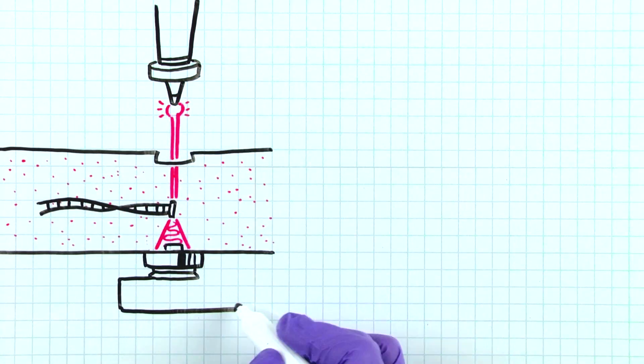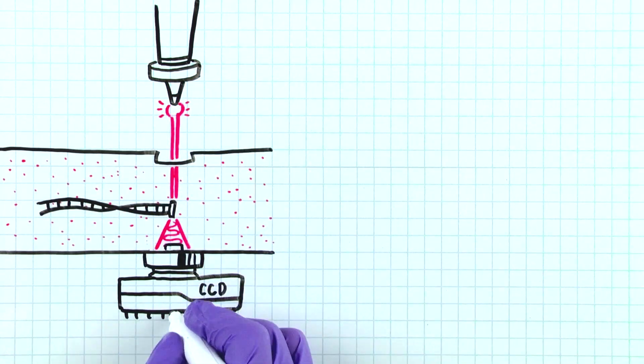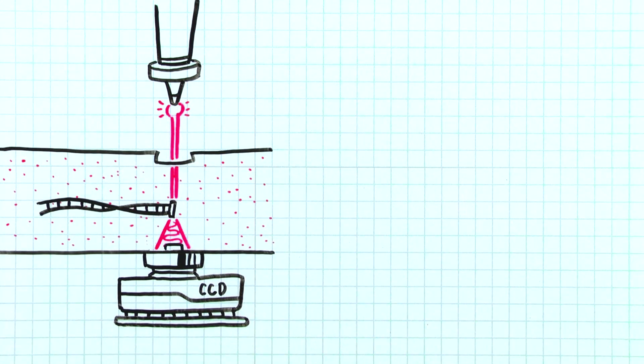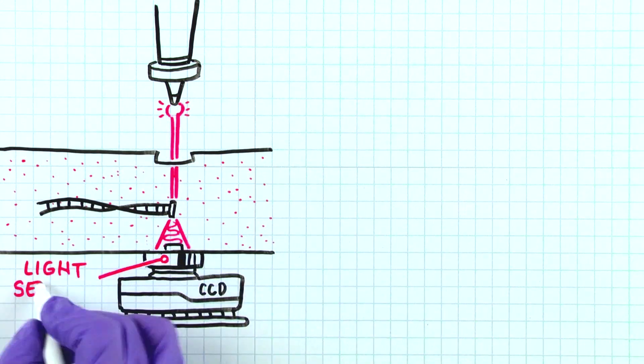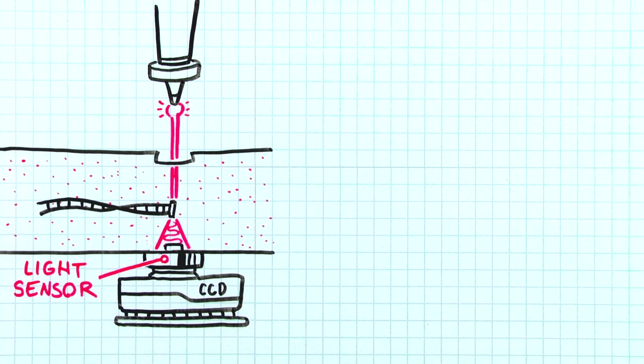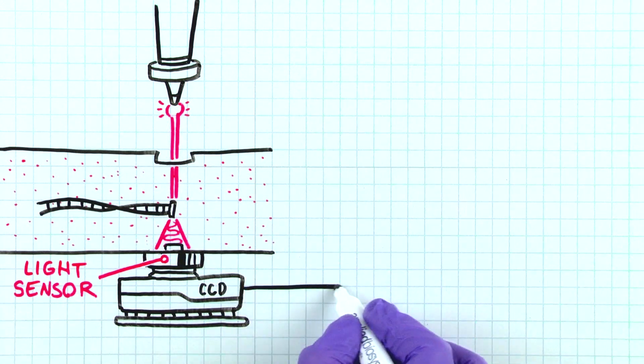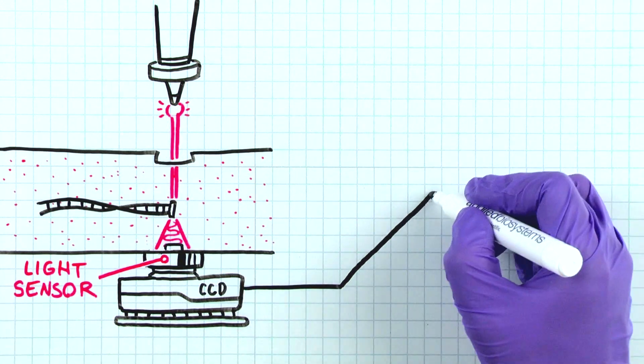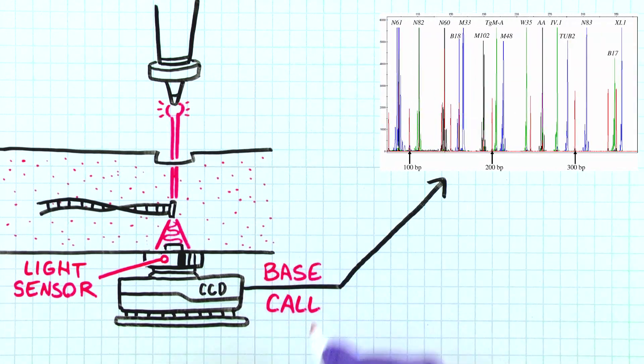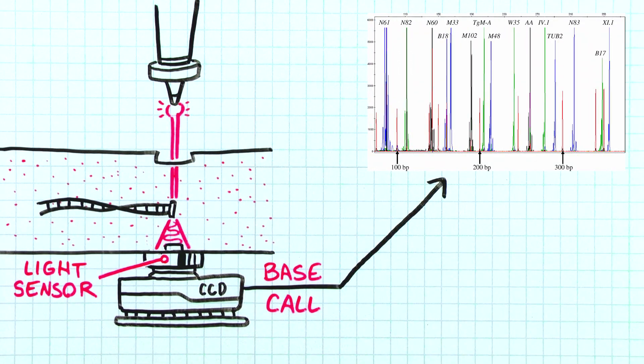The laser beam causes the dyes on the fragments to fluoresce at different emission wavelengths. A CCD camera detects the fluorescence, and the fluorescence intensities are digitalized, color-coded, and displayed as peaks in the electropherogram.